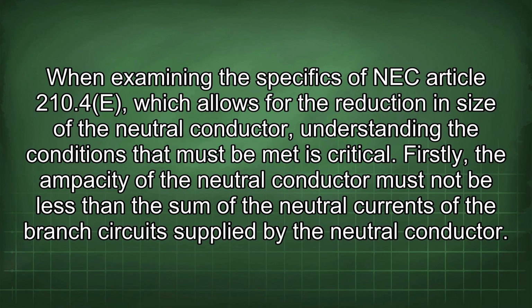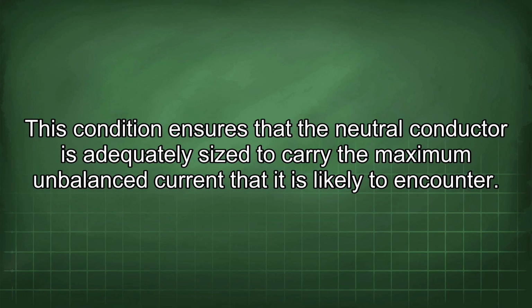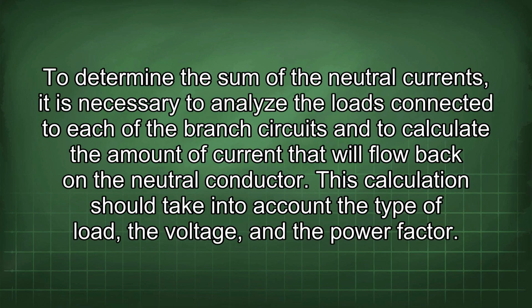When examining the specifics of NEC Article 210.4(E), which allows for the reduction in size of the neutral conductor, understanding the conditions that must be met is critical. Firstly, the ampacity of the neutral conductor must not be less than the sum of the neutral currents of the branch circuits supplied by the neutral conductor. This condition ensures that the neutral conductor is adequately sized to carry the maximum unbalanced current that it is likely to encounter. To determine the sum of the neutral currents, it is necessary to analyze the loads connected to each of the branch circuits and to calculate the amount of current that will flow back on the neutral conductor. This calculation should take into account the type of load, the voltage, and the power factor.